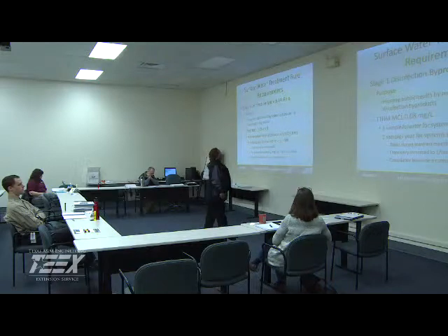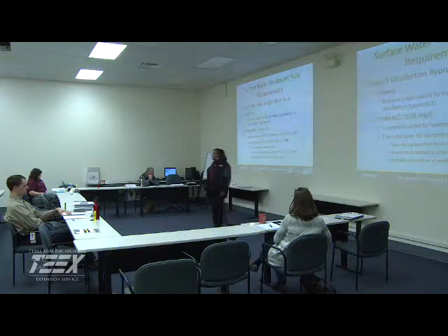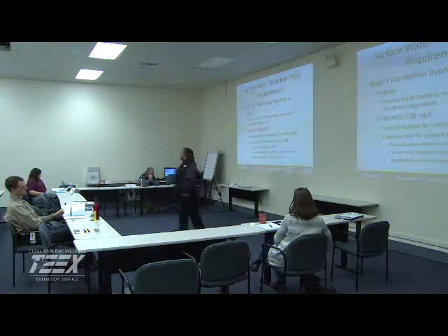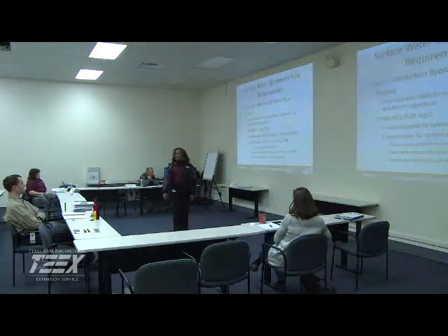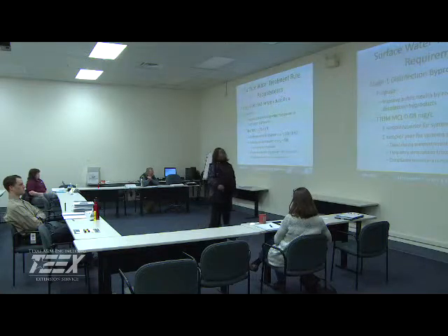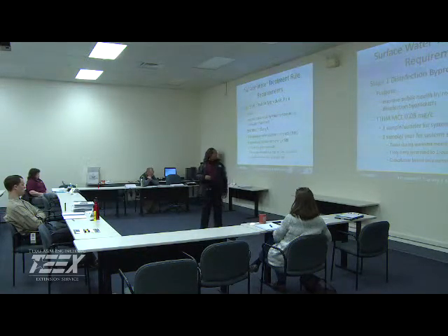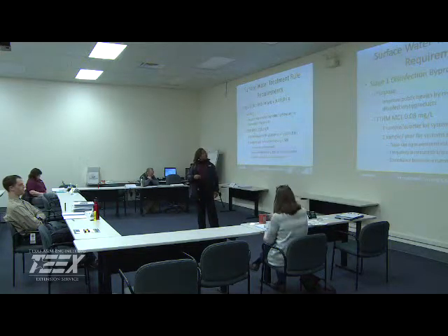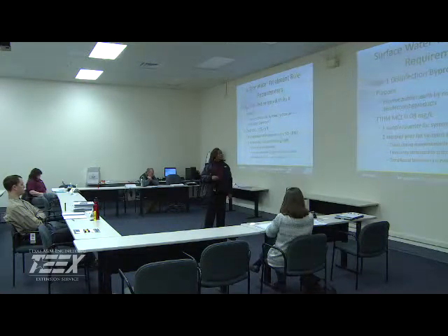All right, with the stage 1 disinfection byproduct rule, again, we're trying to minimize and reduce those disinfectant byproducts that are formed when we have an excessive amount of chlorine and all this naturally occurring organic matter, leaves, algae, and stuff like that, and produce a byproduct which can be a cancer risk and has been shown to be a carcinogen to laboratory animals. So we're looking at total trihalomethanes, maximum contaminant level of 0.08.